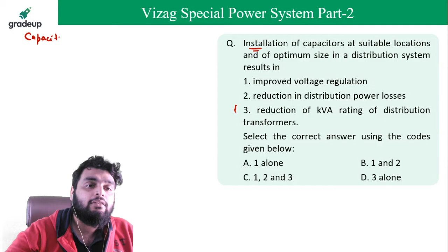If you apply a capacitor, what is the first result you know? When you apply the capacitor, the power factor will increase. That everyone knows, right? For example, earlier the power factor is 0.8. If you apply the capacitor, it will increase from 0.8 to 0.85 or 0.9, any value. Now, what is the kVA rating? kVA rating is equal to kilowatt rating divided by cos phi. Very important point.